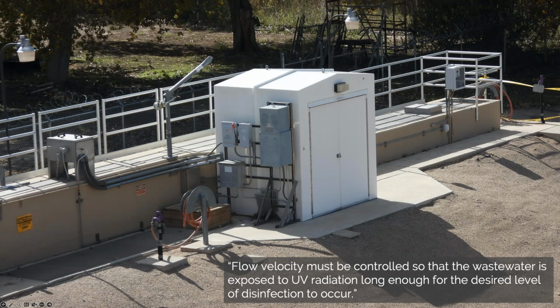But same thing goes for something like disinfection. This is a UV disinfection train. Water moves from the left to the right across the screen and is exposed to UV light, which sterilizes any microbes that are left in it before it hits the outfall. And to quote the NMED OPSERT manual, flow velocity must be controlled so that the wastewater is exposed to UV radiation long enough for the desired level of disinfection to occur. So essentially, you're adjusting flow rate or the detention time in this particular train to make sure that the treatment is effective.